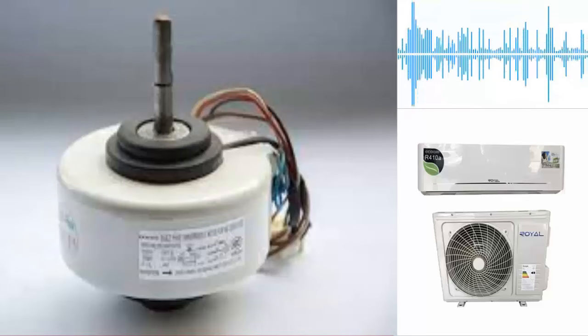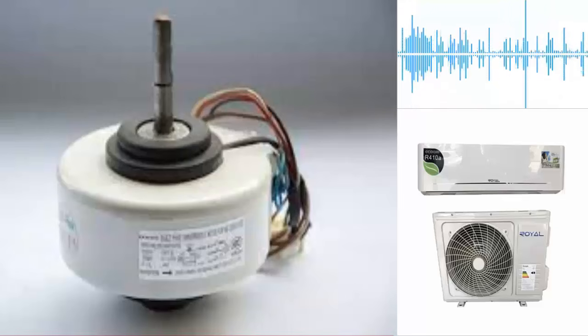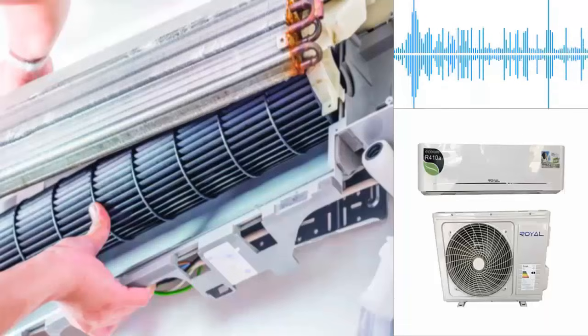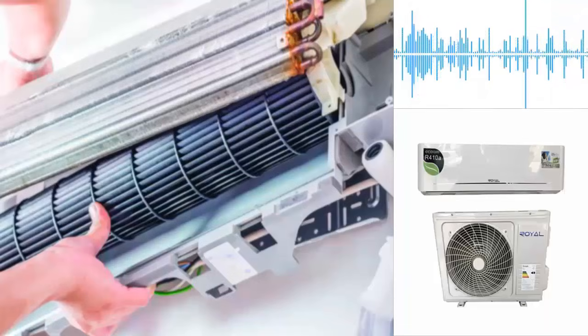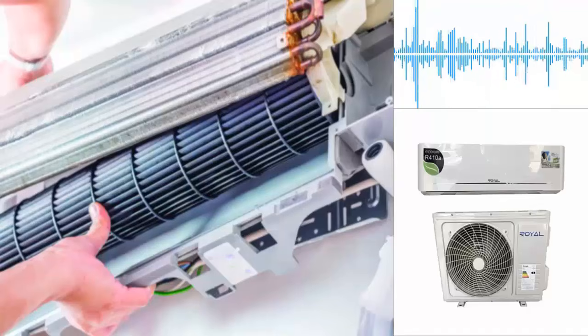B. Check the speed and cleanliness of the indoor unit's turbine, which can affect the equipment's operation, and may cause high temperature readings, leading to faults incorrectly related to gas shortage.